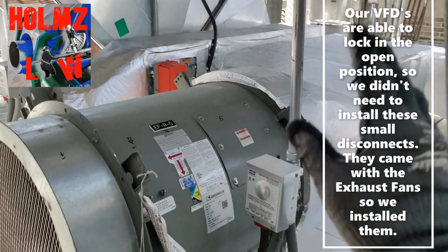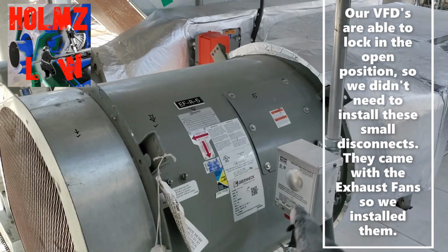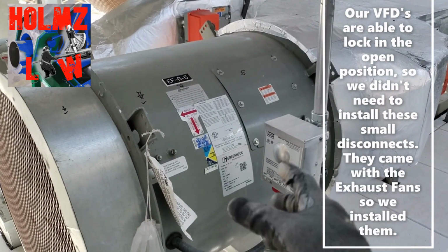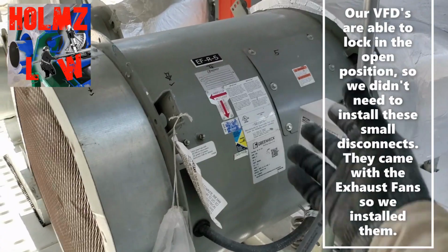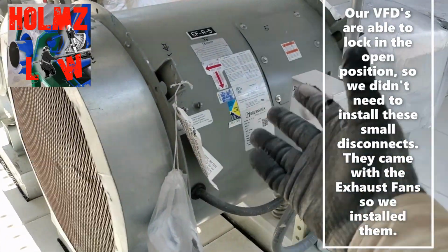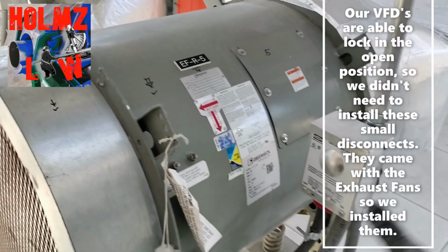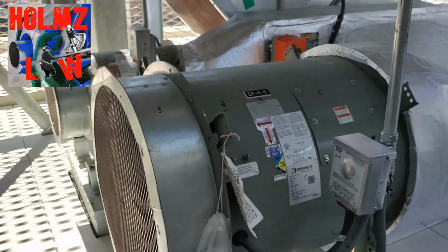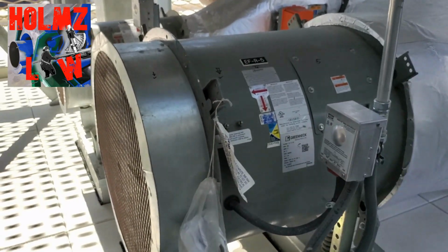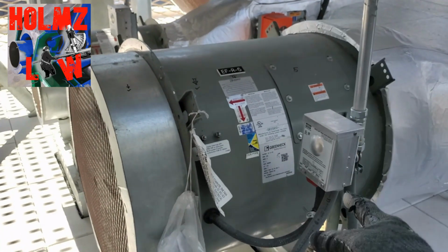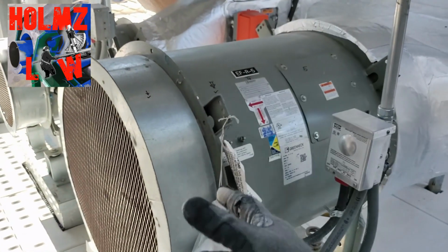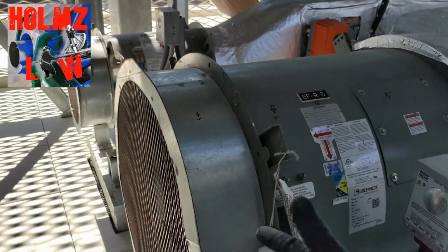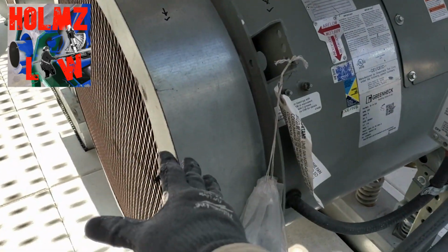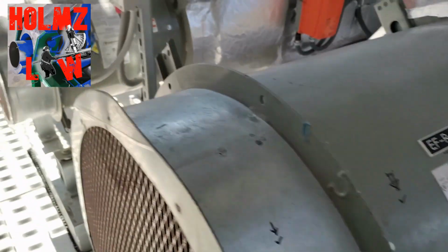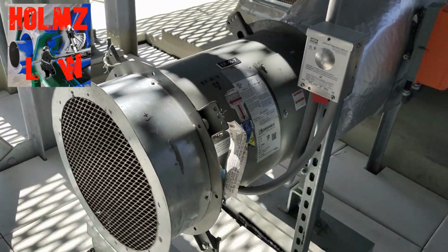Usually you'll also have a service switch, a way to turn off the power in case one of the HVAC guys needs to service it. So even though you have a VFD, most of the time you'll still also have either a toggle switch or some kind of disconnect to turn off the actual power from the exhaust fan nearby. Being that the exhaust fan is here, they'll want a means to turn it off right next to it as well. That's how it usually is.